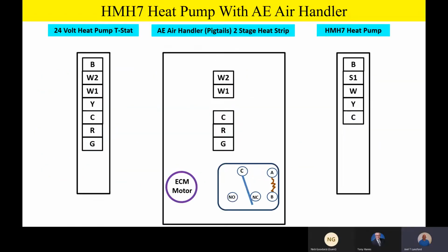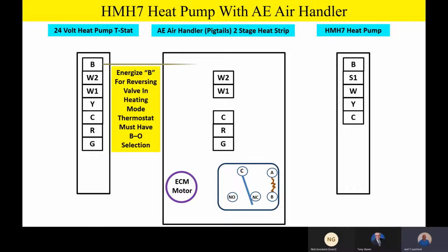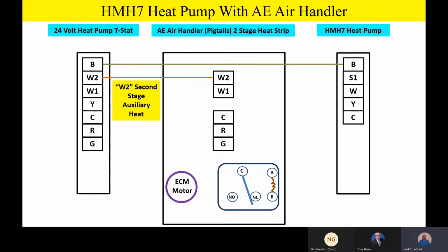Okay, so in a heat pump application with an AE air handler, the whole enchilada, that B terminal is going to go outside to energize the reversing valve in the heating mode of operation, as we mentioned. The W2 will be our second stage auxiliary heat. Our W1 will be our first stage auxiliary heat. Now on a heat pump application, we're going to make sure and bring that W wire from the outdoor back inside as well, so that we can bring the heat strip on during defrost, because we want to make sure that when we go into defrost that we don't freeze the homeowner out.